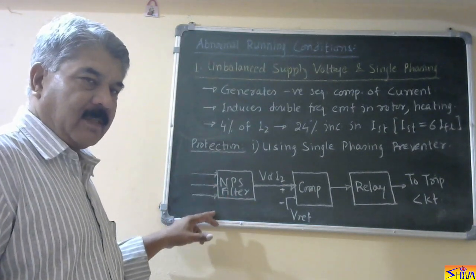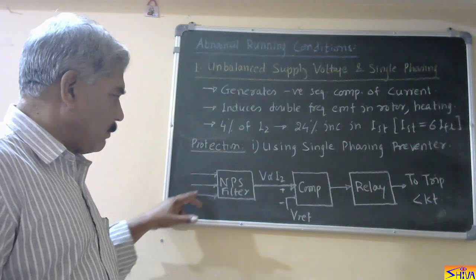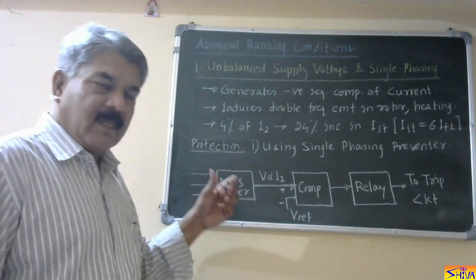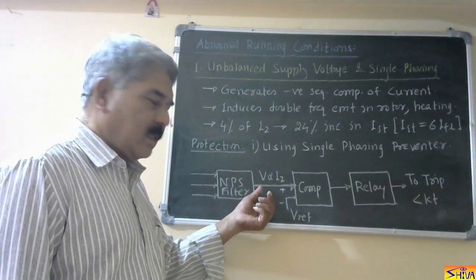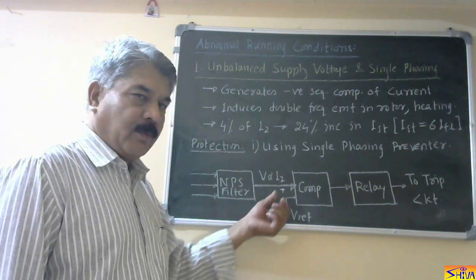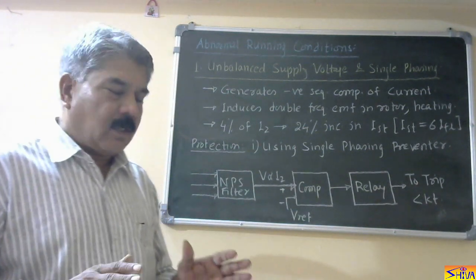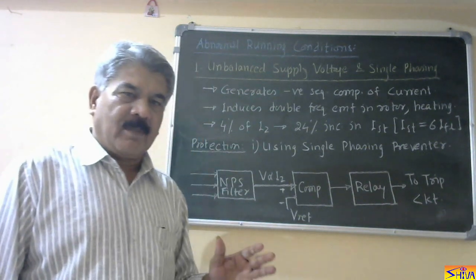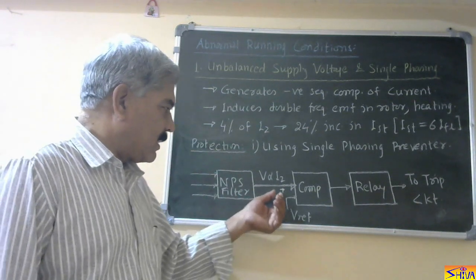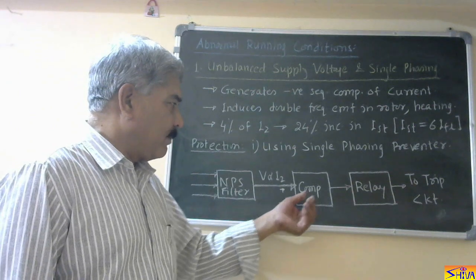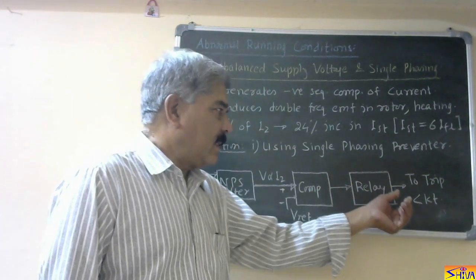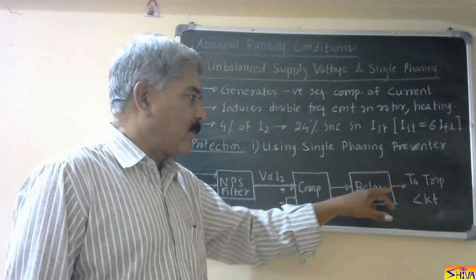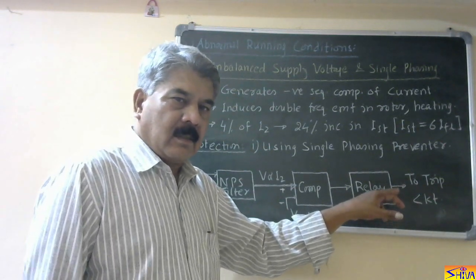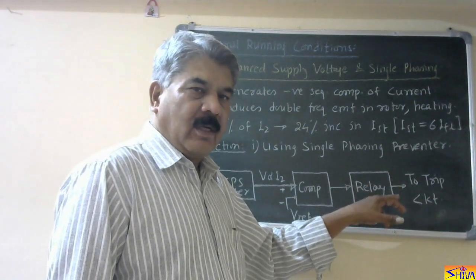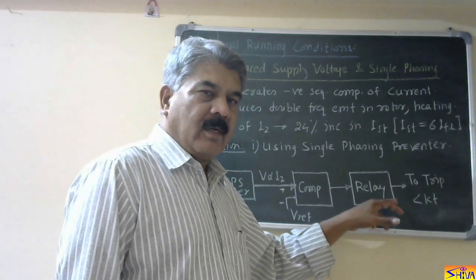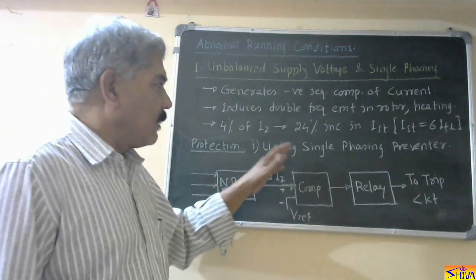So when unbalanced supply voltage or single phasing is there, this negative phase sequence filter is energized by the negative phase sequence component of the current. These currents come from the secondary of the CT. This filter is the same as used for generator protection, and it gives an output voltage proportional to the negative phase sequence component of the current. For some unbalanced loading or unbalanced supply voltage, the motor is not required to be tripped. Some unbalancing is always permitted, but if it exceeds a certain predetermined value proportional to V reference, then the comparator output becomes high. This trips the relay, and this trips the motor from the circuit. The output of this relay goes to the circuit which energizes the contactor coil or MCB coil or MCCB coil or circuit breaker coil. So this is how the single phasing preventer works.